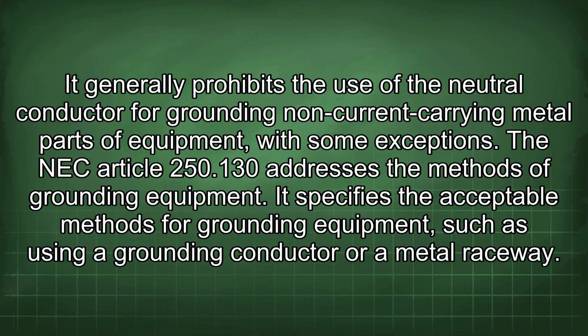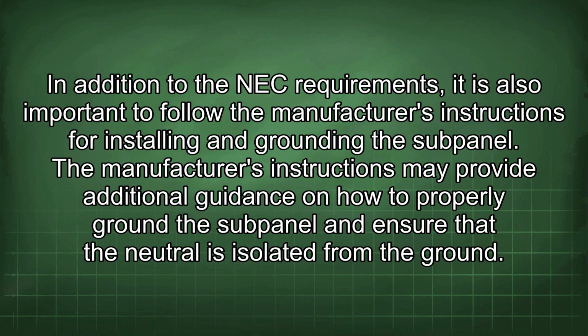The NEC Article 250.130 addresses the methods of grounding equipment. It specifies the acceptable methods for grounding equipment, such as using a grounding conductor or a metal raceway. In addition to the NEC requirements, it is also important to follow the manufacturer's instructions for installing and grounding the subpanel. The manufacturer's instructions may provide additional guidance on how to properly ground the subpanel and ensure that the neutral is isolated from the ground.